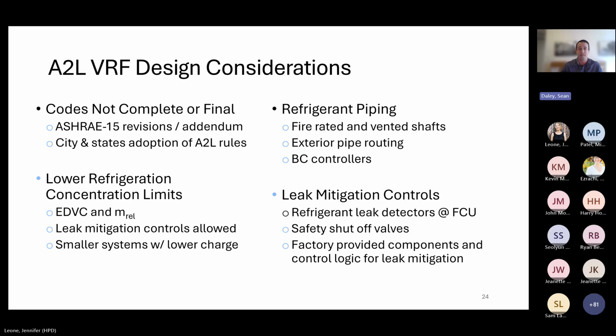And then the cities and states are following behind that. They haven't really set their rules for A2L refrigerants and the safety rules for how they need to be incorporated yet. Again, they're waiting for ASHRAE 15 to make some final determinations, and the cities and states are always a little step behind what the higher-level federal regulations are doing. Next, I touched on it on the previous slide: we're dealing with lower refrigerant concentration limits with the A2L refrigerants, so we introduce those new terms, EDVC and MREL.